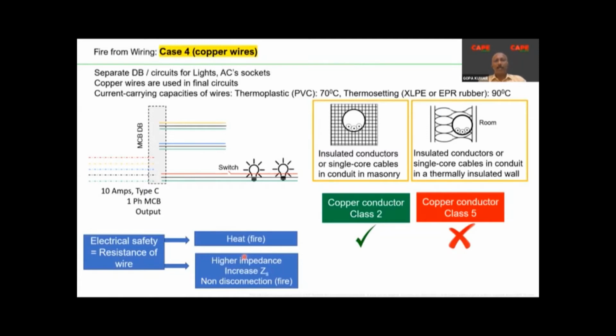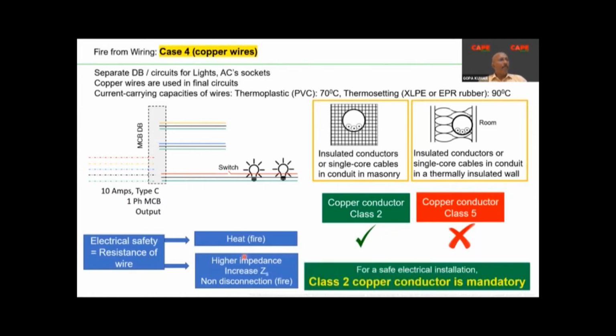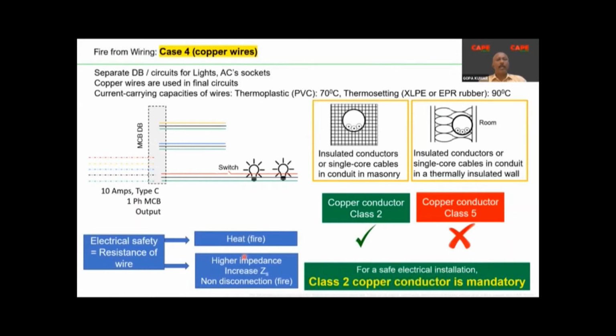Class 5 wires are supposed to be used only for the final cord outlet. If you buy a TV, the extension cord is a class 5 conductor, or probably panel board wiring, you can use a class 5 conductor. Only for short lengths can you use class 5 conductor, not for wiring inside your building. If you use a copper conductor of class 5 in your building, you can be 100% sure that today or tomorrow you will be in trouble.